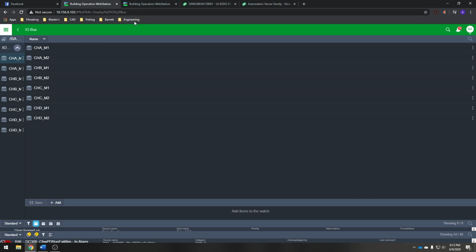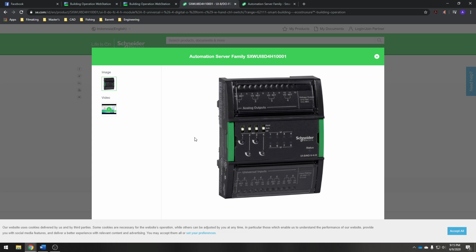So let's say this software is unavailable, something's happened, network's down, something, and we have to control the chillers. We notice something is wrong with the chillers. You walk up to this device right here, and in this pane you'll see that it says chiller A isolation valve. You click that into hand, and this trim pot, if it's spun all the way to the top, all the way around, that's 100%. If you spin it halfway, it'll go to 50, and of course 0. So that's what that potentiometer in there does. That's what controls when you click it in hand.